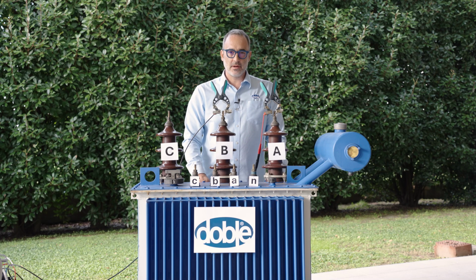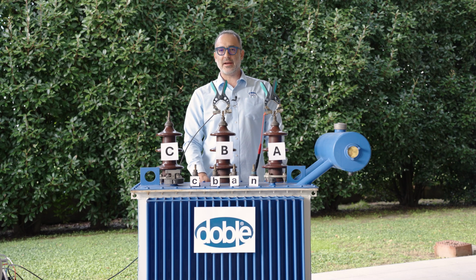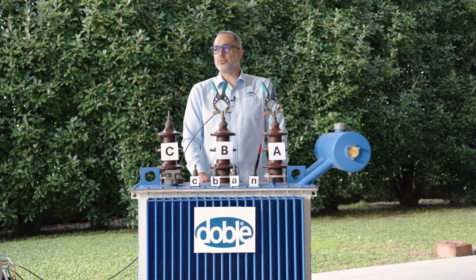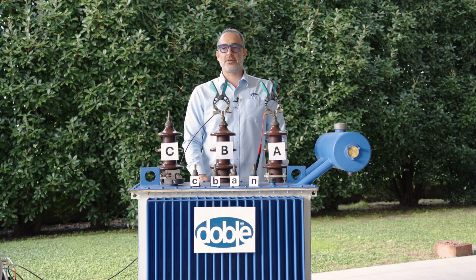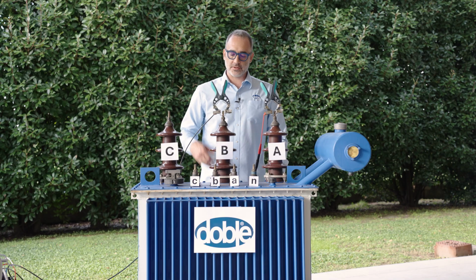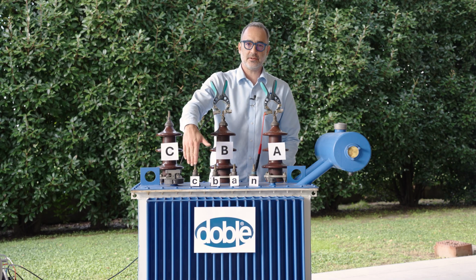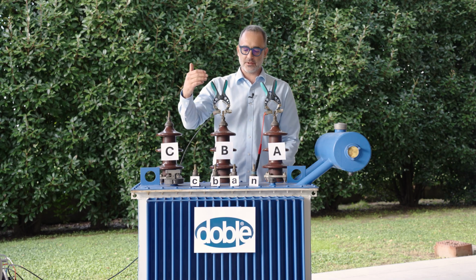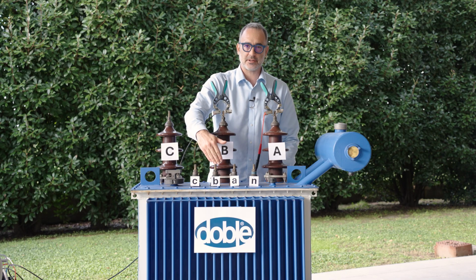No-load test. It's made to find if you have issues with the core. Actually, it's used to tell you the losses in the core. And how do we do it? The secondary side is disconnected, and we generate on the primary side with the secondary side disconnected.